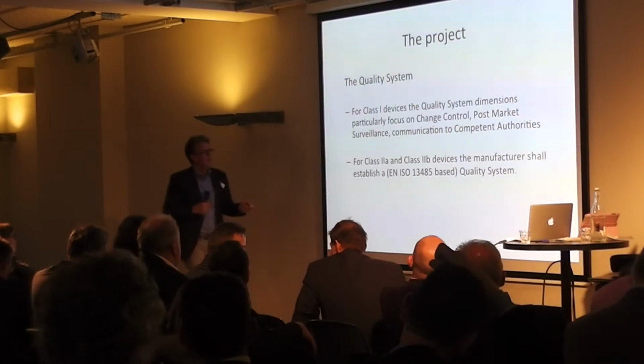For class 1 devices, the mandatory part is that you need to take care of change control, post-marketing and communication to the authorities. And for the higher classes, you need to build in a formal quality system.